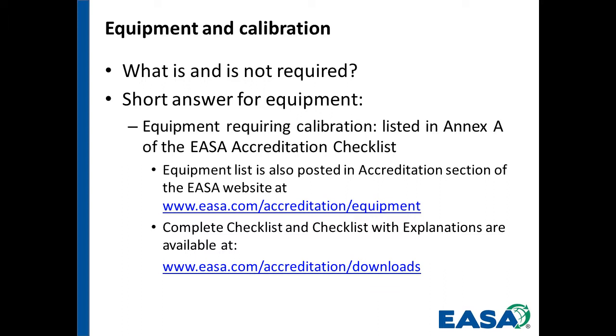So what is and what isn't required? Really what's required is whatever's on the calibration list, the equipment list, that's in the checklist. There's an Annex A, and you can see these website addresses here. You don't really need to write them down. Just go on the accreditation page. That's a drop-down, a push-button click on the EASA website, www.easa.com, and you can get into accreditation, the equipment, go into that annex, and whatever's on there in terms of equipment, that's what you need. And again, things like that watt meter, maybe you need it, maybe you don't. But you need a watt meter in some form, especially for core loss testing there. It's either built into the core tester, or you would need a separate meter if you're doing loop tests.